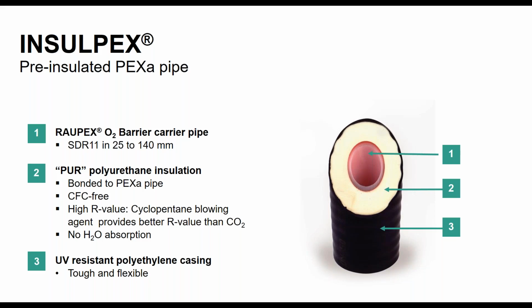On the outside of that is a polyurethane foam — a bonded polyurethane foam. It's actually bonded to the carrier pipe, to the PEX, and in turn also bonded to the outside of the low density jacket, the outside corrugated jacket. That prevents the carrier pipe from moving independently. The foam and the jacket are all bonded together, which goes a long way toward addressing thermal expansion, which we'll talk about later. The foam itself is almost 100% waterproof, which is important because it doesn't allow wicking of moisture down the length of the carrier pipe, which would offset some of the heating capability it would otherwise have.